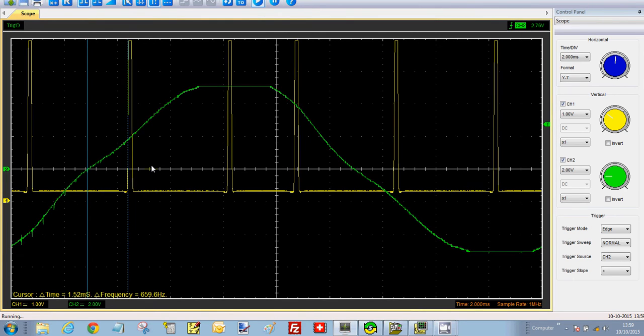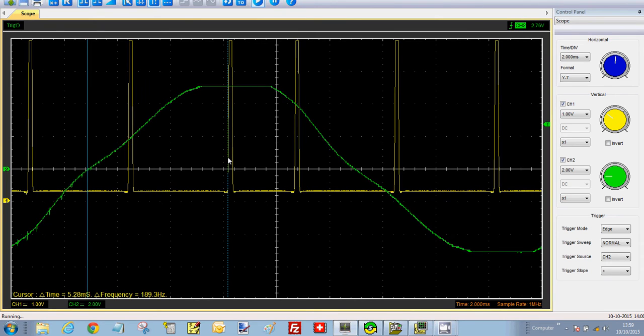Right, now that's aligned. Now if we go back and get the 0 again, the beginning of the short pulse should align at 5.27. We look down there, 5.28, 5.27, so that's fine as well. So there's your mains peak. It always appears flat on these. The mains peak is going to be curved slightly like that. So the beginning of the short pulse is firing at the right place. The beginning of the long pulse is firing at the right place, both with respect to the 0 crossing.